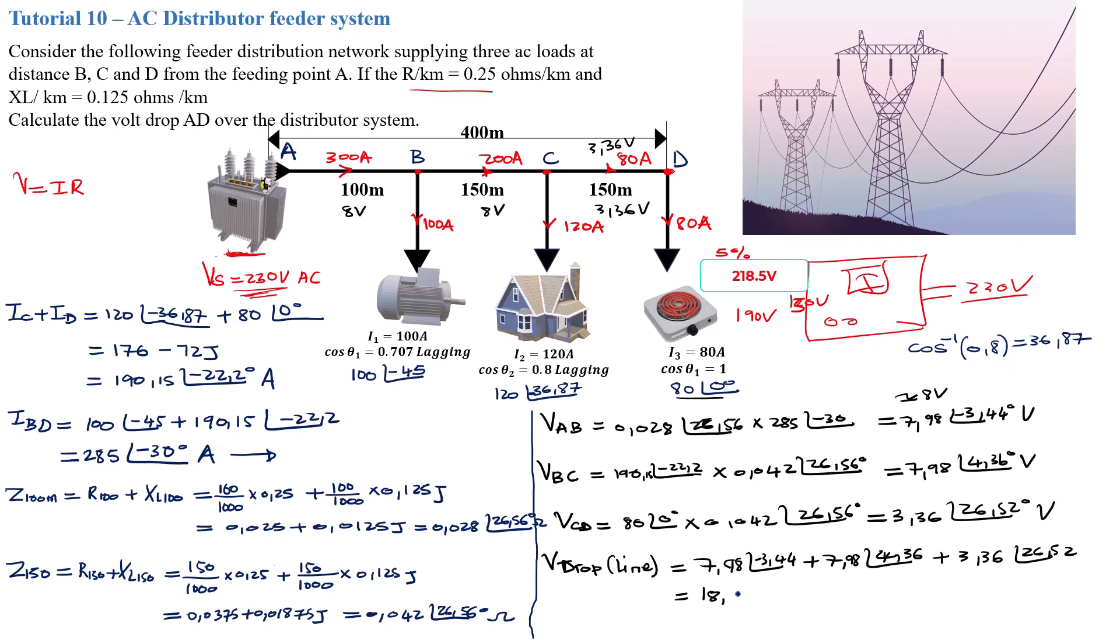Summing all of this up gives you a voltage drop of 18.99 with an angle of 4.9 degrees. You can basically approximate this to be 19 volts with an angle of 5 degrees. So that is basically the voltage drop across this line here.